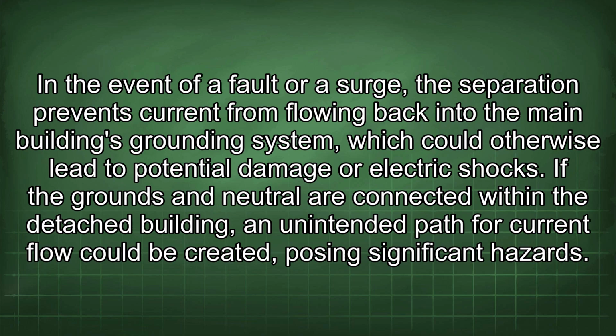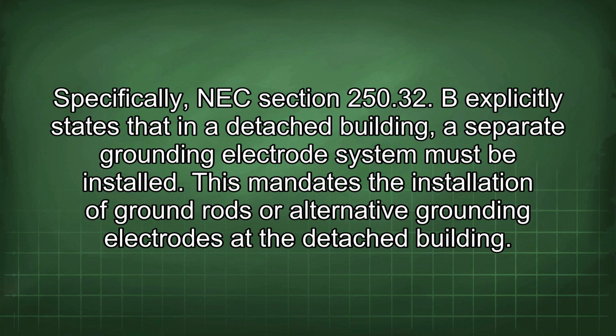In the event of a fault or a surge, the separation prevents current from flowing back into the main building's grounding system, which could otherwise lead to potential damage or electric shocks. If the grounds and neutral are connected within the detached building, an unintended path for current flow could be created, posing significant hazards. Specifically, NEC Section 250.32 B explicitly states that in a detached building, a separate grounding electrode system must be installed. This mandates the installation of ground rods or alternative grounding electrodes at the detached building.